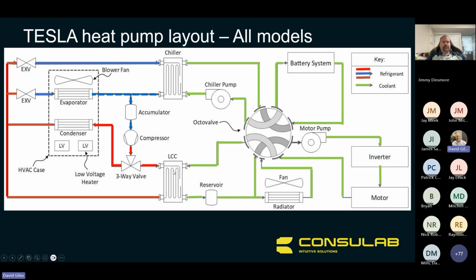These components here, the LCC which is our liquid cooled condenser, and our chiller, basically separate the system. Inside the air box is the evaporator, and then we have the condenser. They're both inside, and it's just a regular type of condenser. Obviously it's not huge, it's small, it's very efficient, as well as the evaporator.